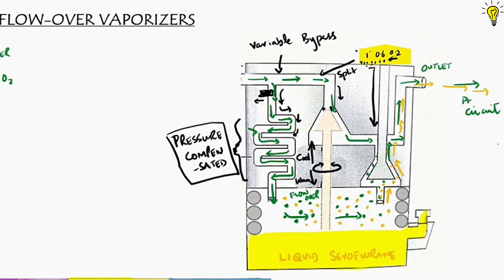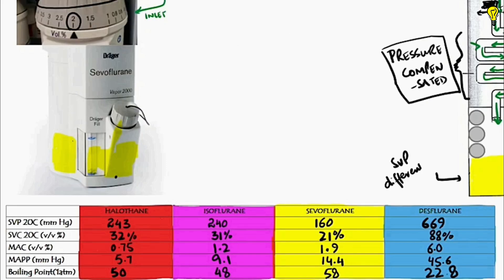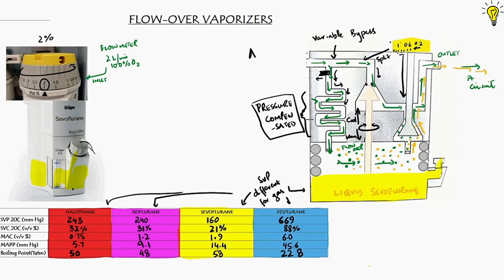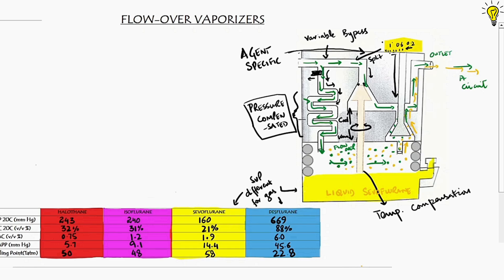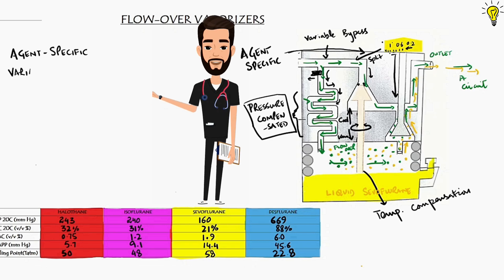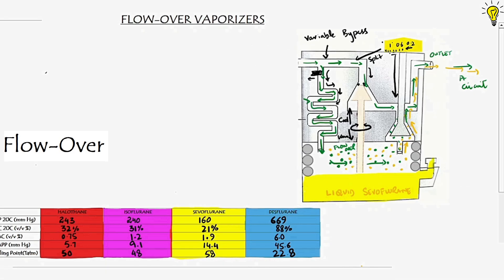The saturated vapor pressure at 20°C is different for different gases, so the amount of flow diverted by the concentration dial must also be different. Every vaporizer is therefore agent-specific. Temperature compensation is achieved by changing the bypass-to-vaporizer flow ratios. So the full name is: agent-specific, variable bypass, temperature and pressure compensated, flow-over vaporizer.